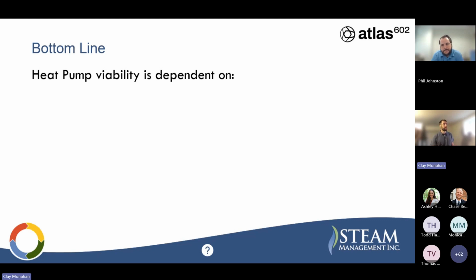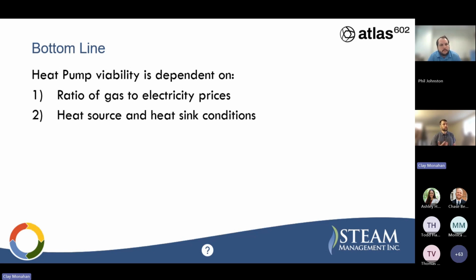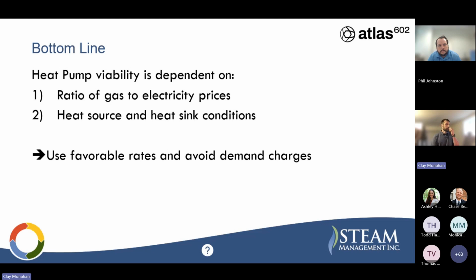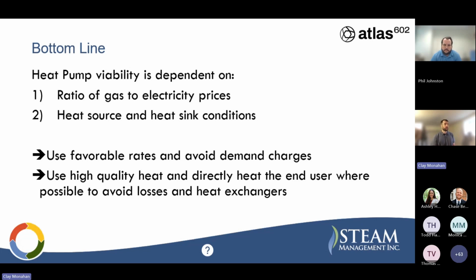I just want to reiterate, heat pump viability is dependent on that ratio of the gas and electricity prices. Like I said, Phil's going to get into that a little bit deeper next. And then the heat source and heat sink conditions. The higher the temperature we can get, the lower the lift, the better. So use favorable rates; avoiding demand charges can change that effective electricity price significantly. And then using high quality heat and directly heating the end user where possible to avoid losses in a steam system, say, and heat exchangers, that's all good. So those are some high level thoughts. Anything on the theory side? Happy to field a few more questions before Phil gets into some more real world applications of these theories.